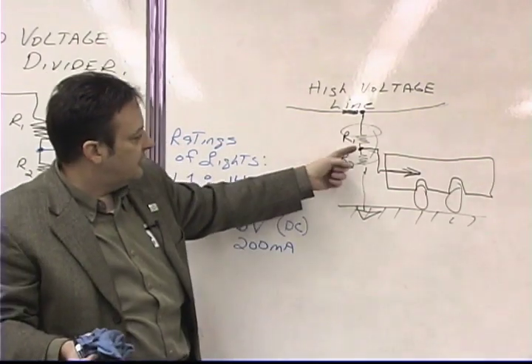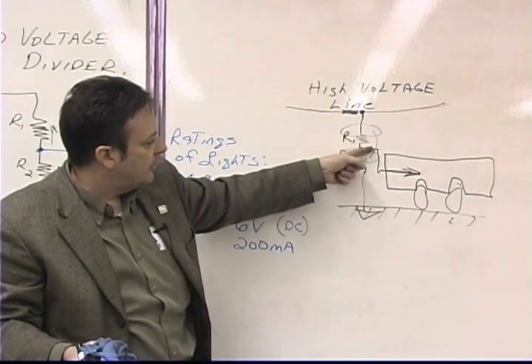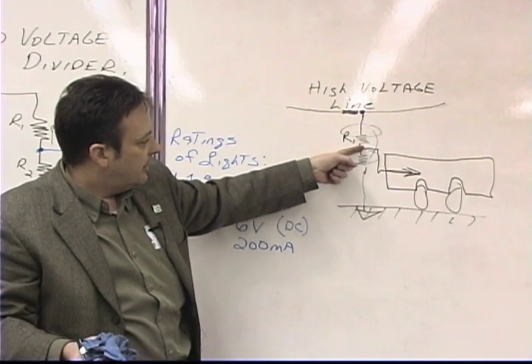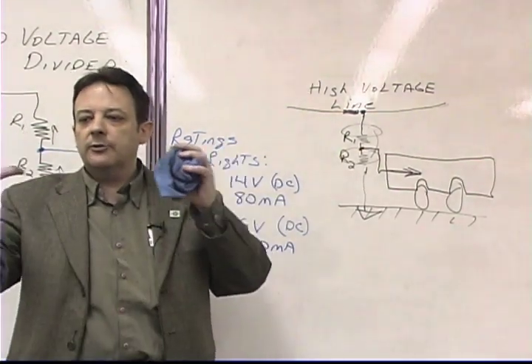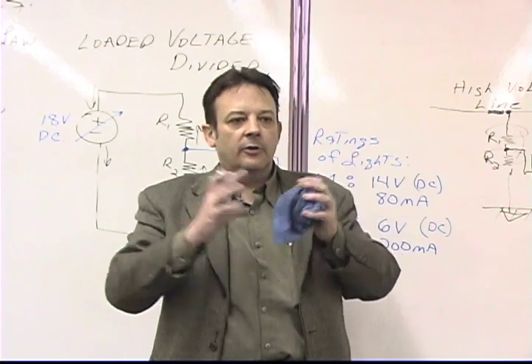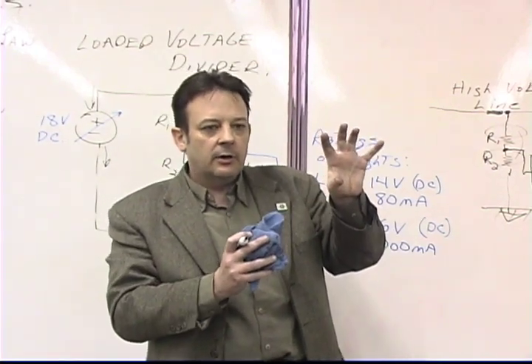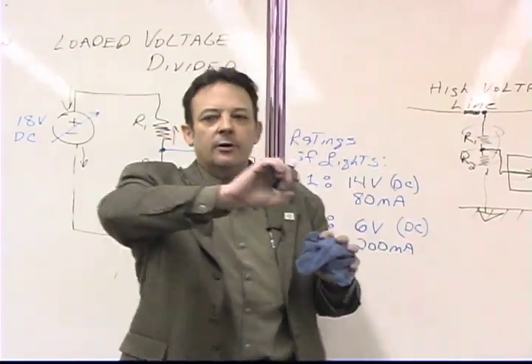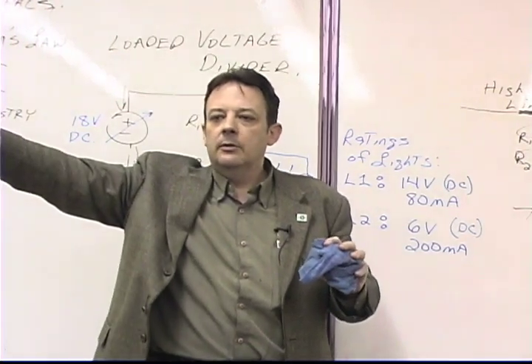So what all utilities do now is use fiber optics. They feed the signal coming out of the voltage divider into a fiber optic transmitter, and then run like 500 feet of fiber optic cable.